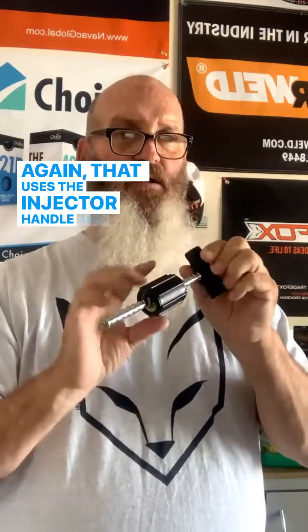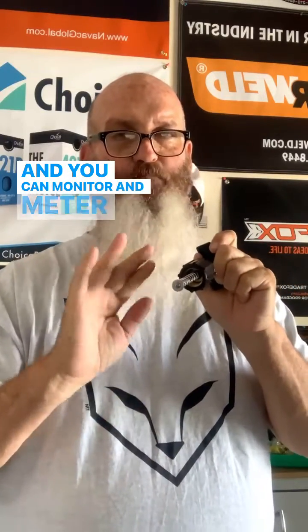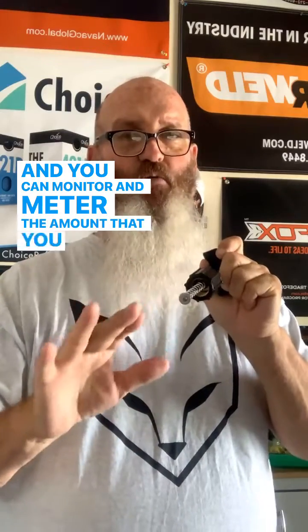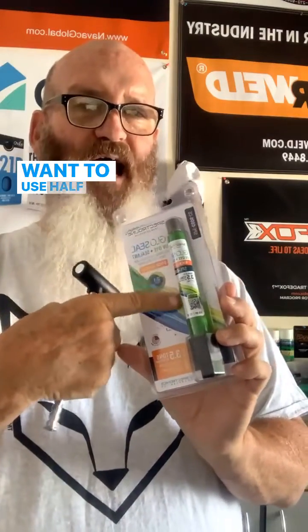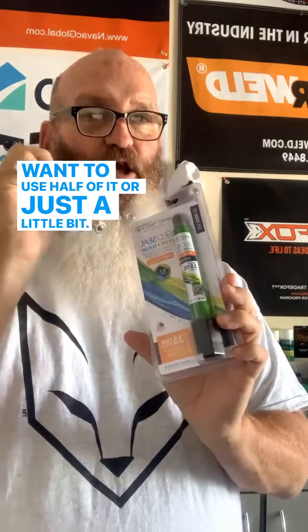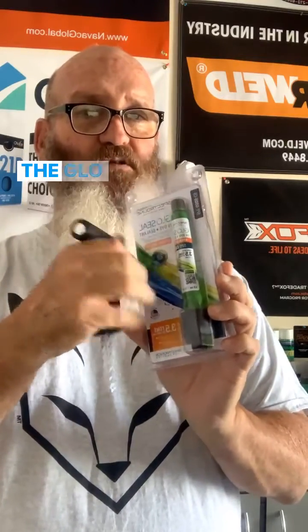The injector handle actually pumps the dye in and you can monitor and meter the amount you want to use. Nobody says you have to use the entire tube — if you have a smaller unit like a ductless split and only want to use half, you can put a little bit in and then reuse the GloSeal and the handle.